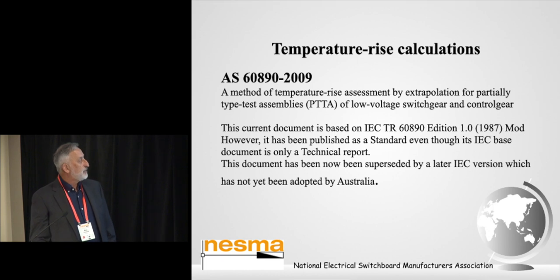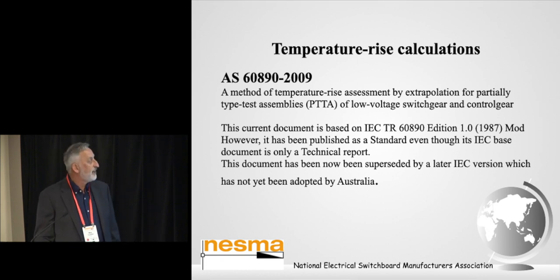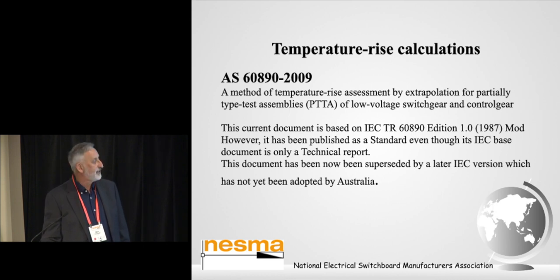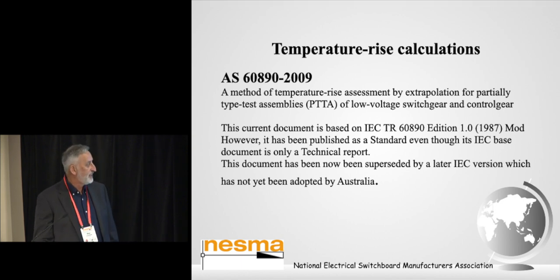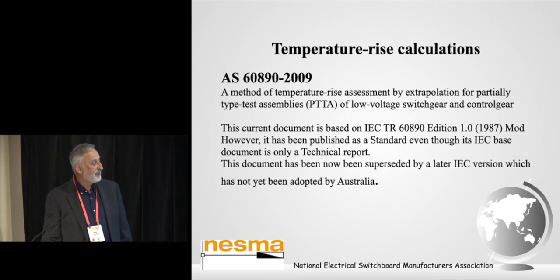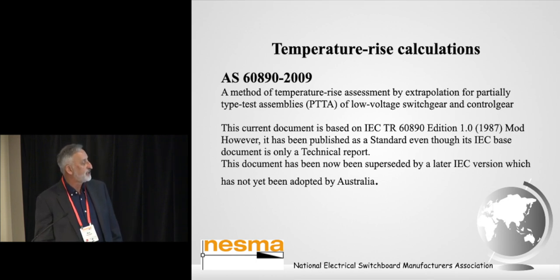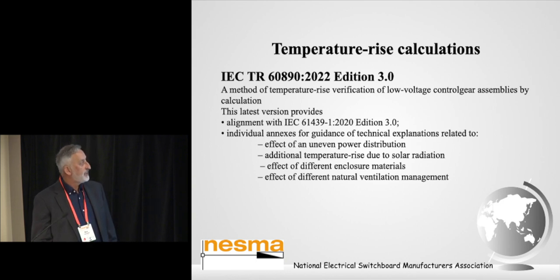Another standard that comes up is the 60890, the 2009 version, which is a method of temperature-rise assessment by extrapolation for partially type-tested assemblies of low voltage switchgear and controlgear. This current document is based on edition 1 of the IEC. However, it has been published as a standard through the IEC, even though it's only a technical report. The parent IEC document has been superseded, but it has not been adopted by Australia as yet. The superseded edition, which is edition 3, is turning into a very useful document.